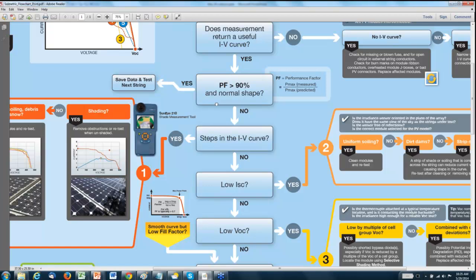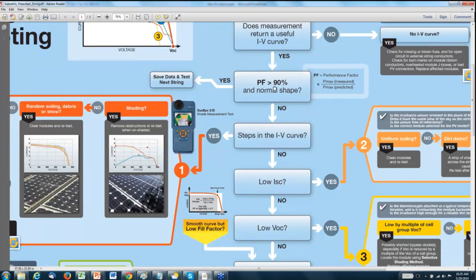If you're in the 90s and it has a normal curve shape and it's pretty much in the same performance factor range as all the other strings you've been measuring, then you exit with the yes and you save your data and move on to the next string. Measure the next string.